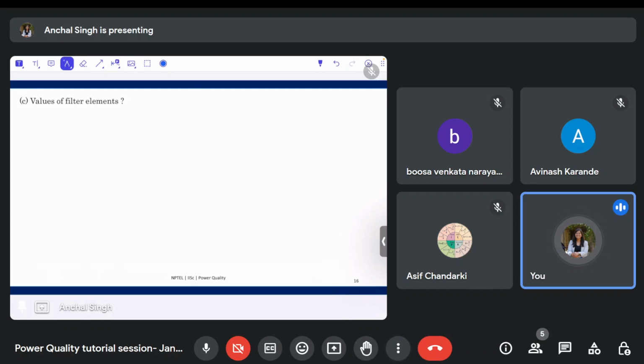Now we are asked to find the value of filter elements. So we have only one high pass filter here, right? And since this is a three-phase circuit, there will be three such branches. So I will divide the total reactive power of my system, which is 112089 vars. That was in kVAR, so I'm converting it into vars. This total reactive power will be divided into three parts because there are three branches, one for each phase.